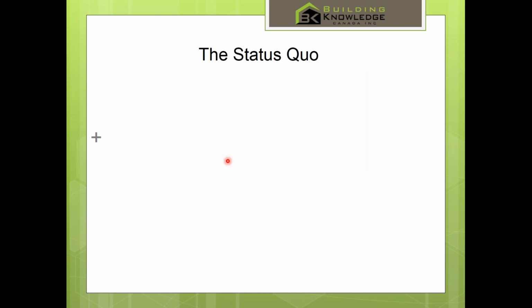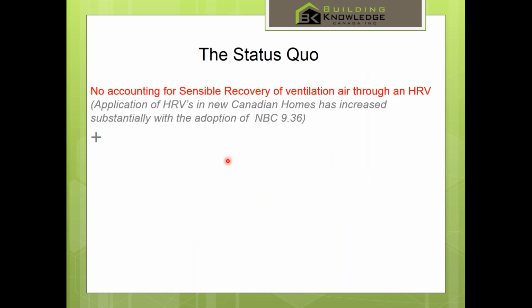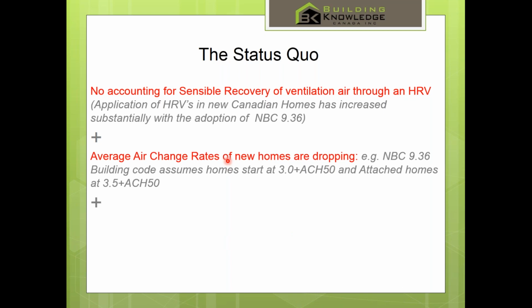So here's what we have. The status quo of where we were a few years ago, before the F280-12 came in, was that when we did heat loss calcs and heat gain calcs for homes, we did not include the heat recovery of an HRV, which we have seen substantial adoption of in homes across Canada, and yet we were not including its efficiency in our heat loss calcs. We have also seen air change rates in homes drop substantially, by virtue of building code addressing requirements for air barrier inspections, which are fairly new to us, and also voluntary programs. In some provinces, we're seeing programs like Energy Star hit 33% market uptake. Anyways, all in all, we're seeing air change drop. Keep in mind that these air change rates have dropped, and yet we really had no way of accounting for it in the old F280.